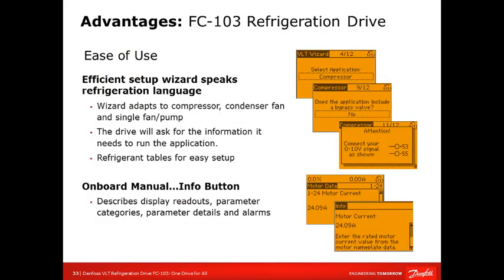For us, what we were trying to show is ease of use. With this 103 refrigeration drive, Danfoss, working with our industrial refrigeration cooling experience, has built a lot of software into the drive, so it's speaking refrigeration language. That's why we put in a setup wizard, to make it very easy to work with in the setup, whether it's a fan, a pump, or a compressor. The drive is actually working with you as you're installing the VFD, setting up and commissioning the drive. The other advantage is there's an onboard manual, which is great. You can hit an info key and it'll help you even with troubleshooting. It'll recommend, in this bottom right hand corner, motor current, so it's informing the operator what to do, for example, when entering a parameter setup in the drive.